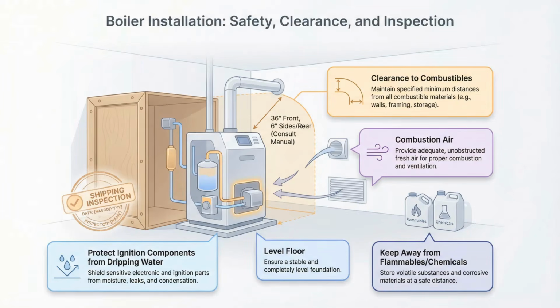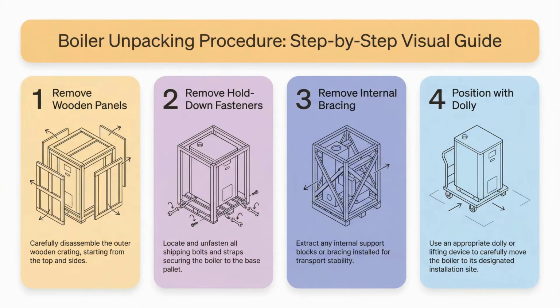Pre-installation is about preventing predictable hazards. Inspect for shipping damage, confirm required clearances to combustibles, both manufacturer minimums and local code, ensure proper combustion air and venting plan, set the boiler on a level surface, and keep it away from flammables, chemicals, and any water that could drip onto ignition components. Unpacking sounds basic, but it matters. Boilers are crated with bracing and hold downs, and manufacturers usually specify the removal sequence so nothing twists or falls. Once the crating is off, then the unit can be moved safely to its final location.